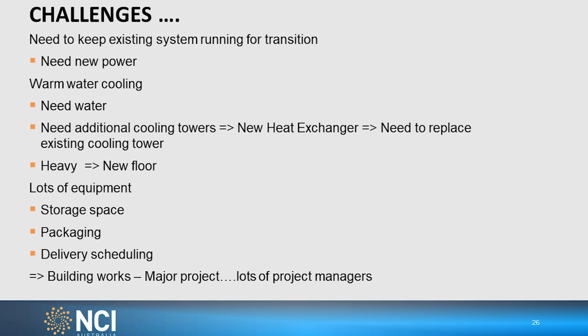It's heavy. As Werner mentioned yesterday, with these direct liquid cooled systems there's just more metal inside the machine, so we're now approaching 2 tons per square meter. An individual rack is around 1,300 kilograms, 600 wide by 1,200 deep, so it's quite a hefty weight in a small space.